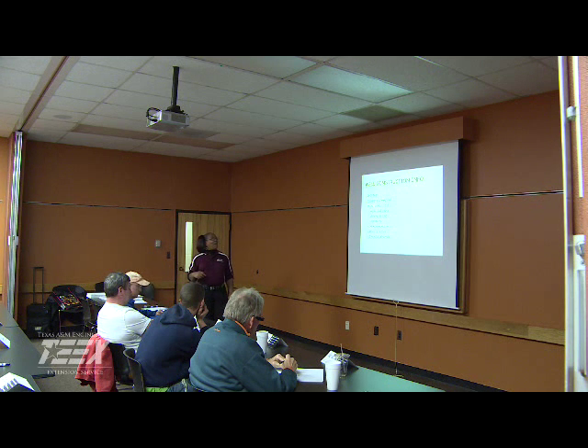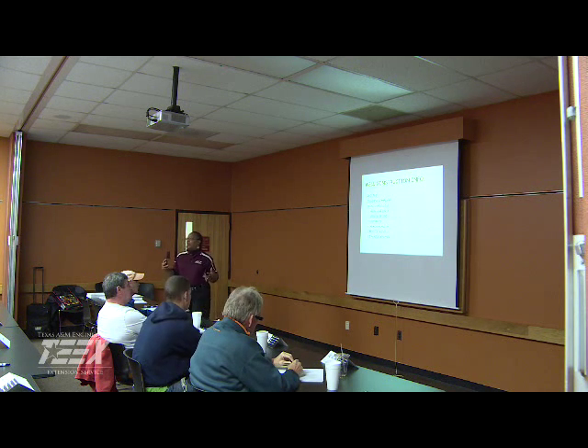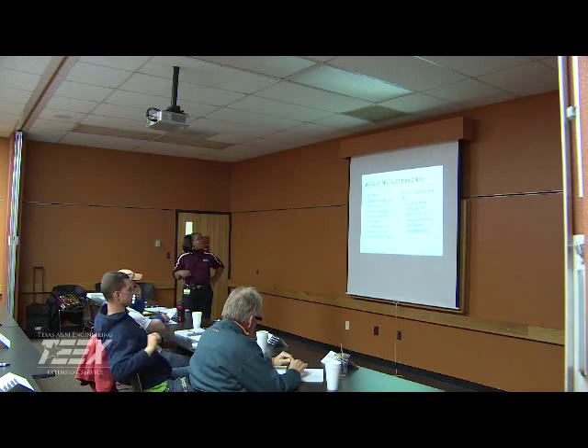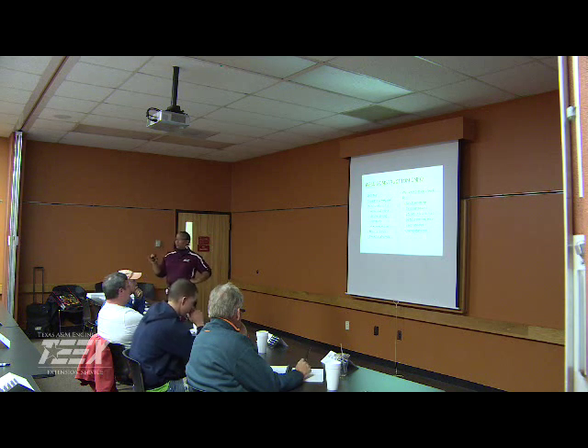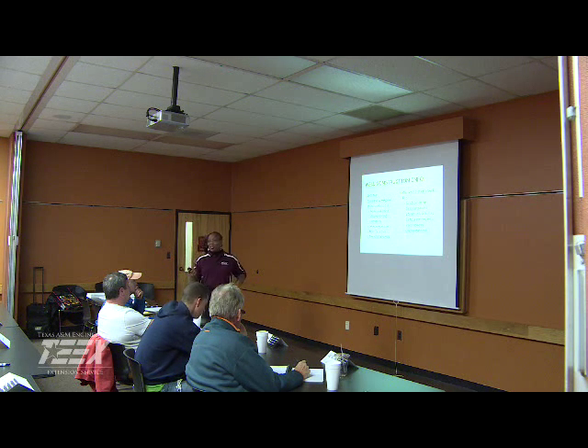All right, now, in your well construction information, as far as the well log, keep in mind we have a baseline of everything after that well has been put into service, or after it's been developed, prior to putting in service. Remember, we're collecting bacteriological and chemical analysis. We're doing a 36-hour pump test. We have the electric logs, material setting, the well size and depth. All of that you should have. The checklist, the deed or ownership, construction data, all of that should be something readily where you can put your hand on it if someone were to ask you to go get it, because there is a stipulation on retention of records.